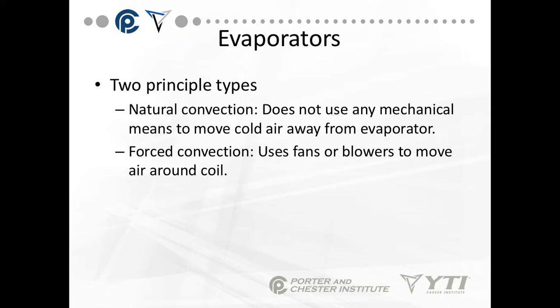Let's start off with what evaporators are and the different types. We have two principal types: natural convection, which doesn't use any mechanical means to move air through the evaporator, and forced convection, which uses fans or blowers. Natural convection is found heavily in extremely heavy process cooling or frozen food warehouses. Forced convection is the one you're going to find most frequently.